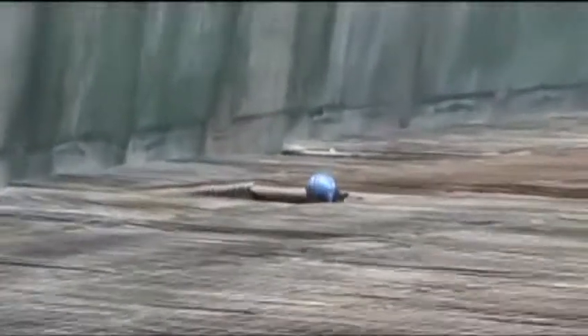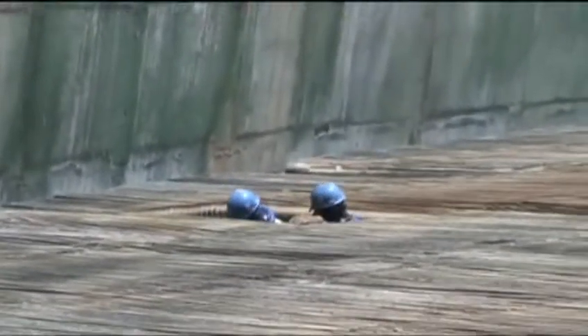You get an idea here as to how they're standing on top of the fill material, working on cutting the piping. You hear it echo as it falls out, and they're breaking it as they're sending it out of the bottom. It's only about 4 feet between the bottom of the drift eliminator and the top of the fill.